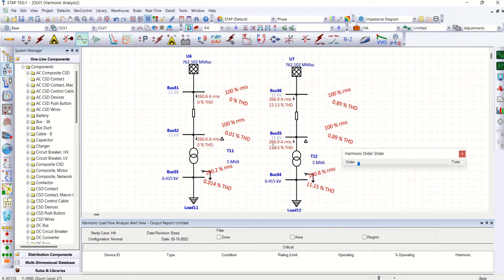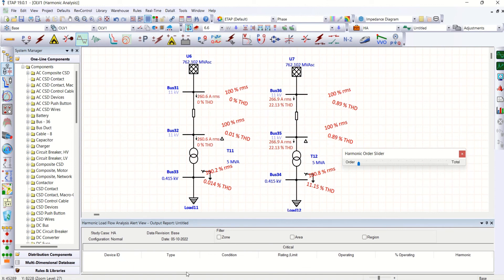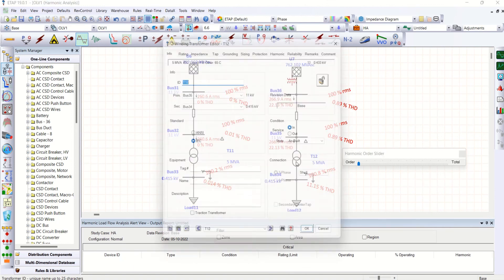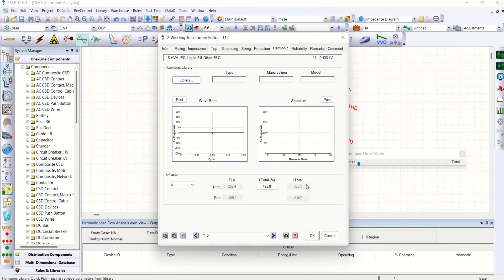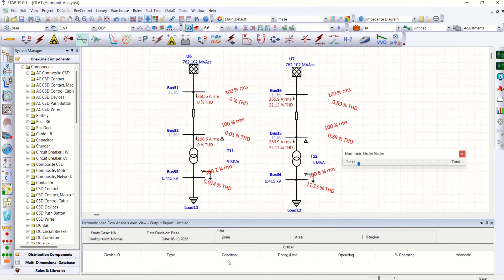Now still, this transformer is overloaded or that is handled by K4 rated transformer. Now though it is 266.9, have a look at this alert page, alert page showing nothing. Because the transformer is not overloaded. Transformer can handle the current up to 330.1. That is the reason why it is not showing anything.